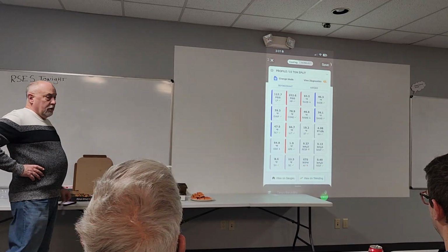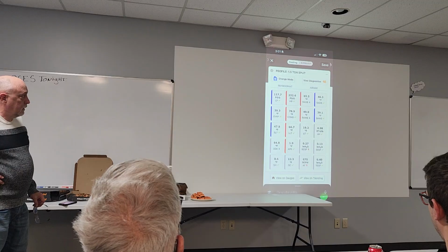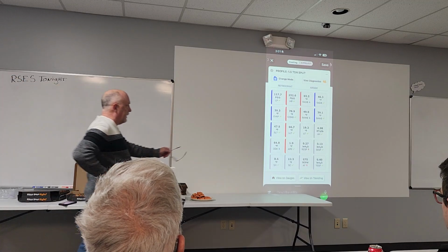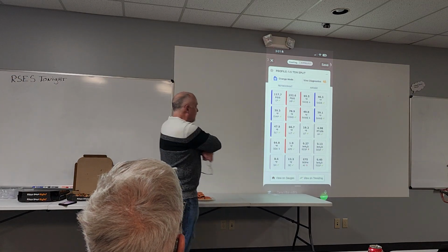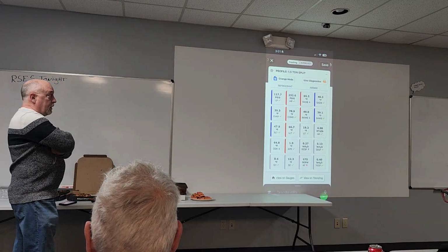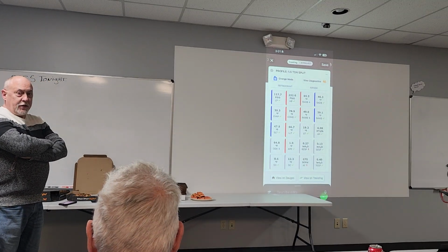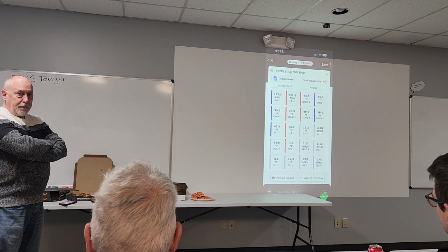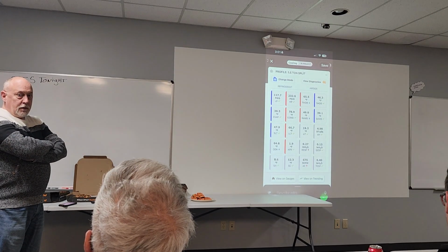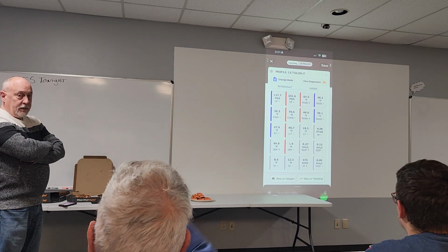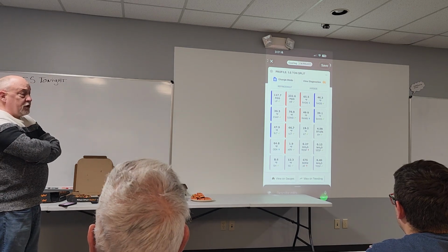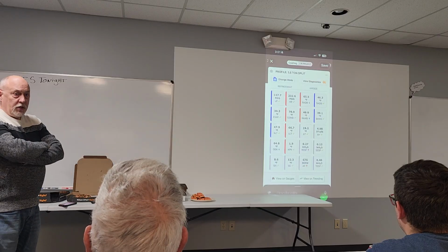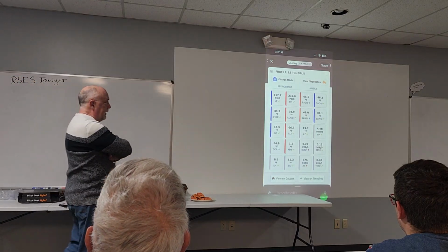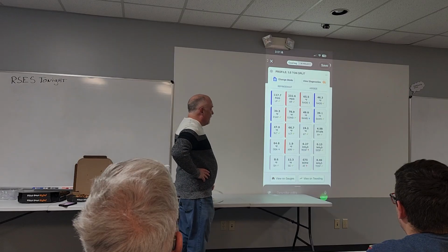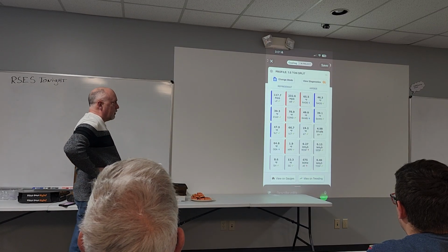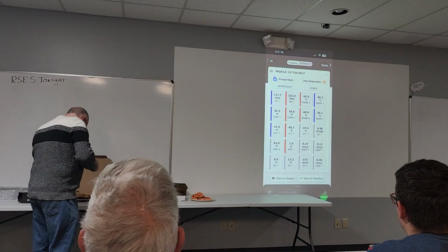Where's the condensing, or the outdoor air temp in this? Outdoor air temperature is right here, 65 degrees, 64 point. So you've got low head to start with. And what's that going to give us? You're on the right track. Suction pressure is going to be low because you have low head. We have an oversized evaporator in this thing, but differential pressure across the metering device is low. Typically we want about 160 pounds across the metering device. Right here, we have about 115 pounds or so across the metering device, so that's another reason we're going to have low capacity.